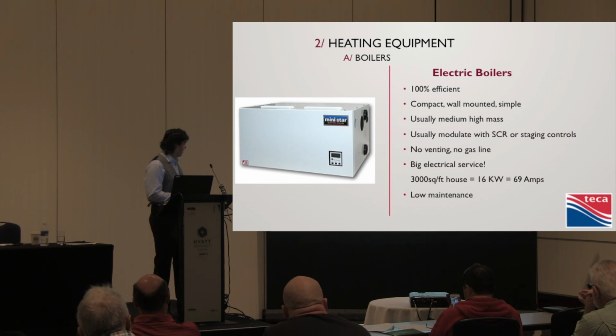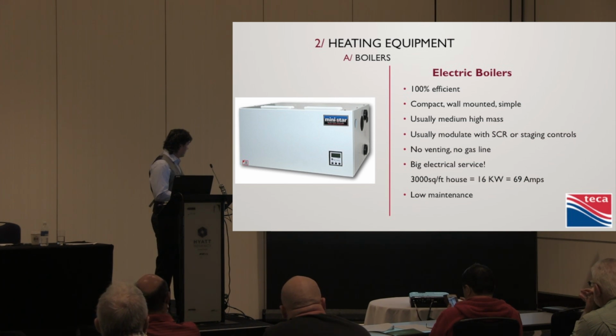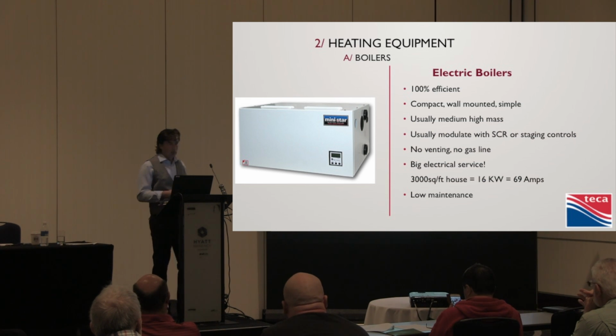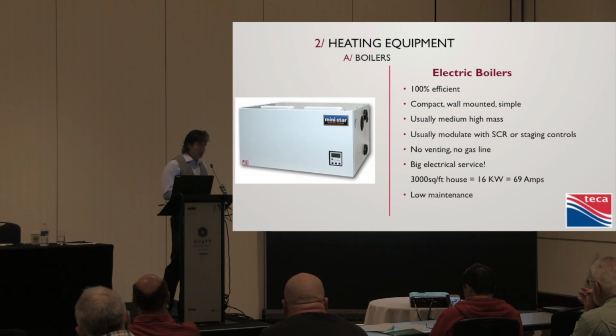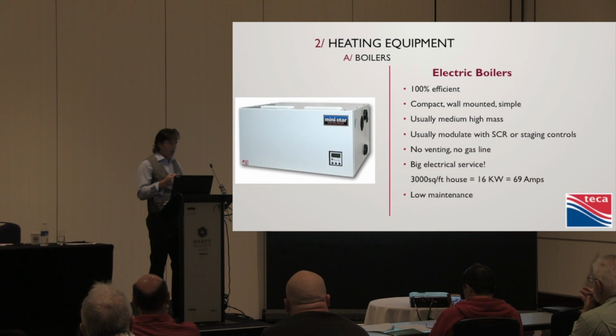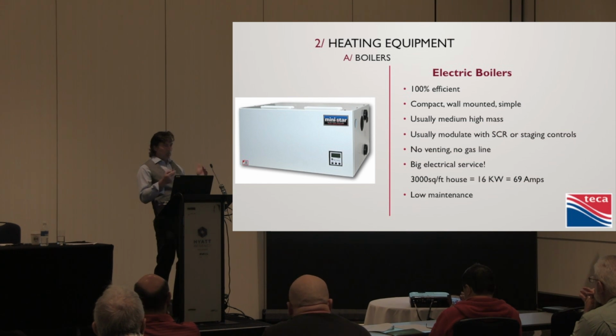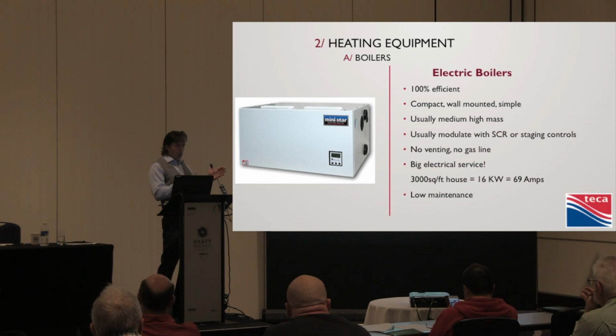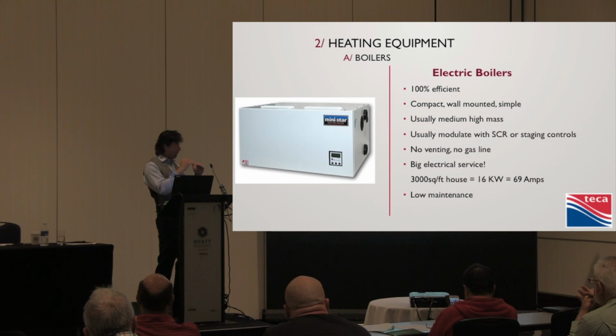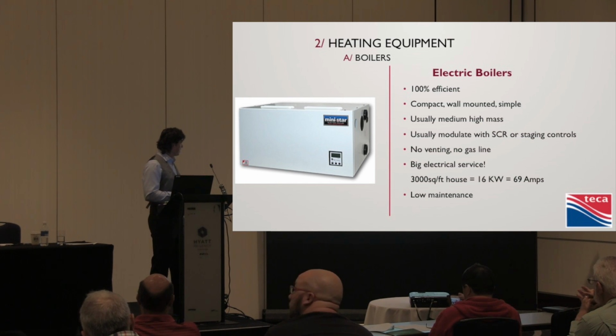These things, the way they make them now, this one right here is actually a Tecmar control, but they usually modulate with SCR or staging controls of some sort. This boiler, let's say it's 18 kilowatts, it'll have at least three 6 kilowatt elements in it. So by the same principle that condensing boilers want to modulate, we should modulate these too. You don't come on with 18 kilowatts every time. You want to slowly bring that up and adjust for efficiency.